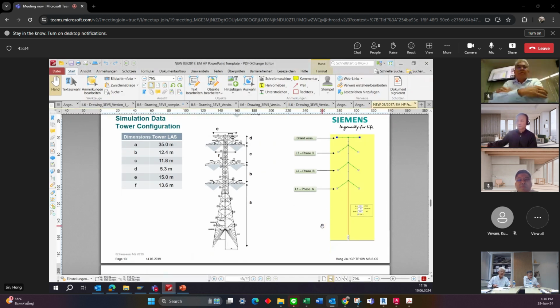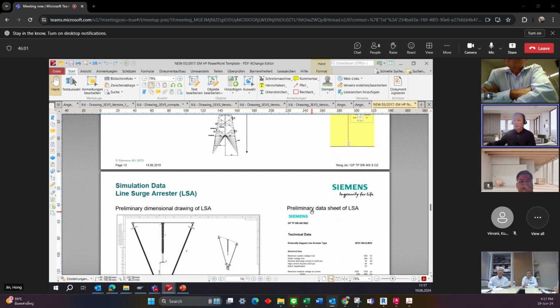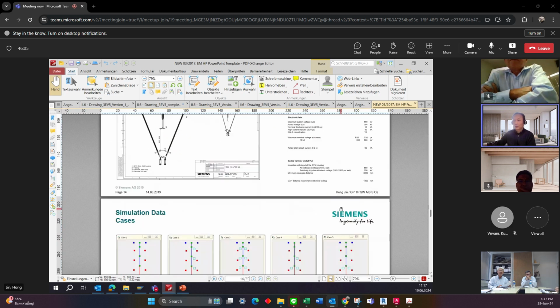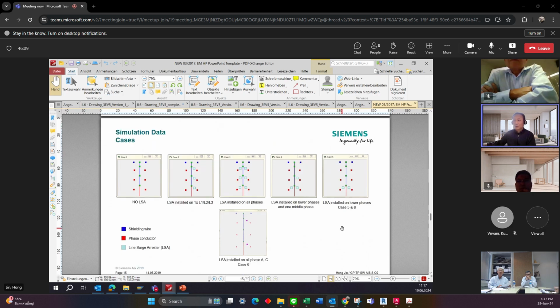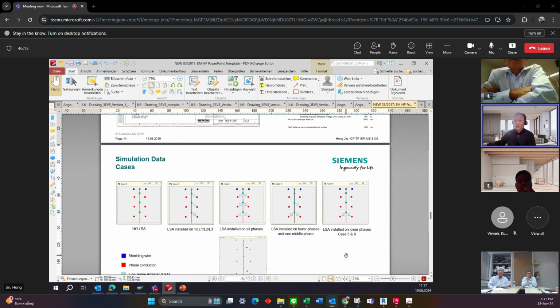Yes, to specify the requirement from the construction specification. Our requirement from the owner is that they need the tower. We have a questionnaire. In the questionnaire, we have listed all the required data, including the tower configuration and also the footing resistance for each tower, and with those inputs of the data. Because it will take a very long time to prepare the modeling of the line study, to get all those data from your side to be input in the software. This is the first step. And then if we finish the input, we will start running the software simulation, it will take several days.